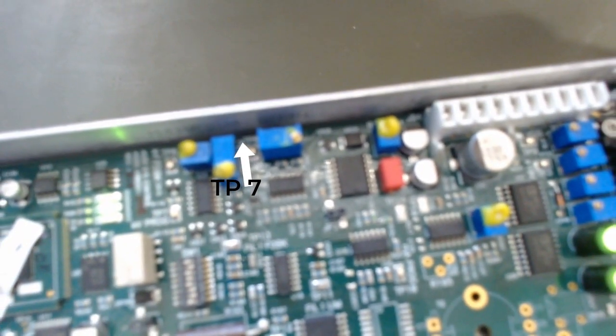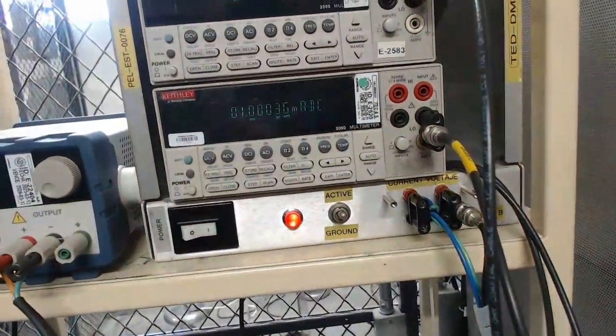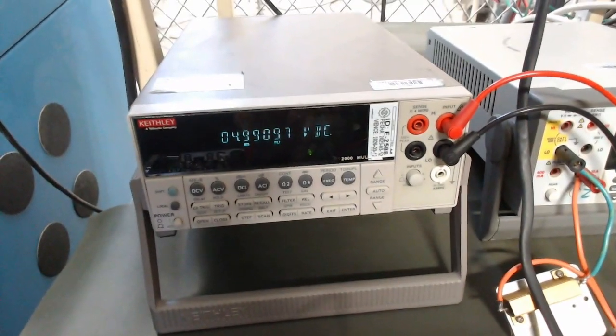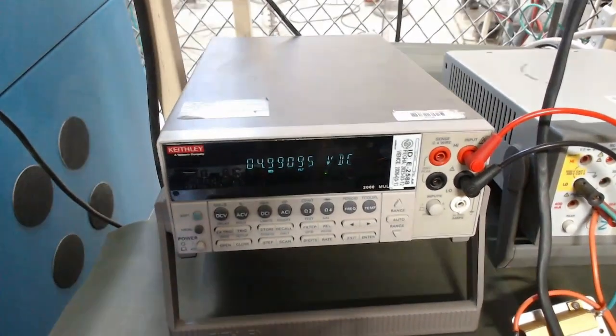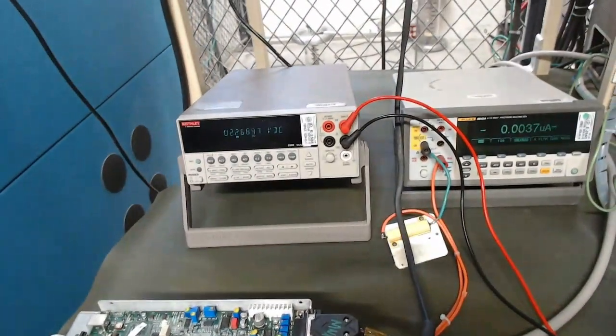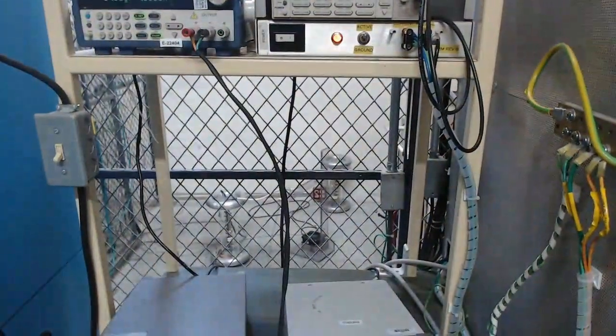Reason for measuring at TP7 and not at the 15-pin connector is because the current monitor signal that goes to the 15-pin connector is not available unless operating under an X-ray tube. This will be performed later. It can be seen that 4.990 volts are reached in the current monitor signal at 1 milliamp. Value is recorded in the datasheet, and we can proceed to the next test.